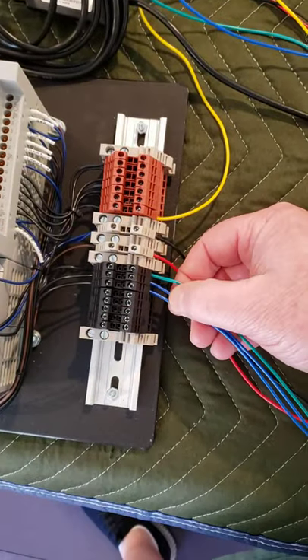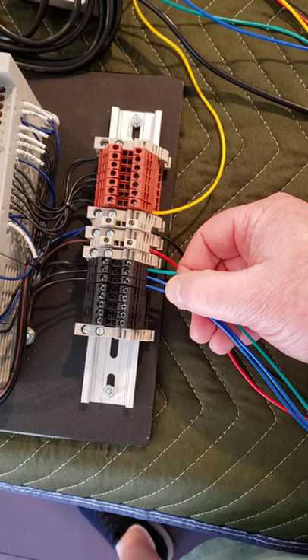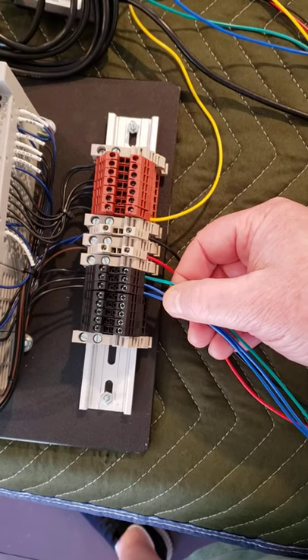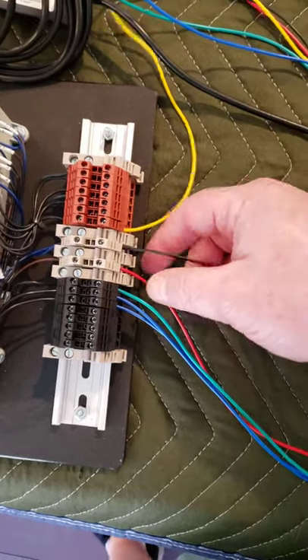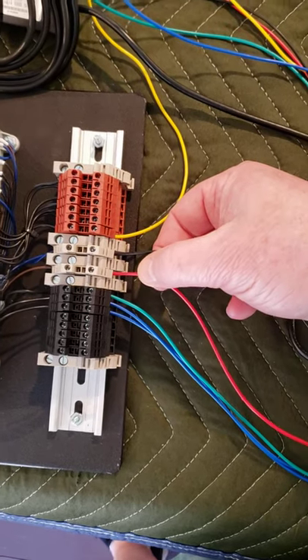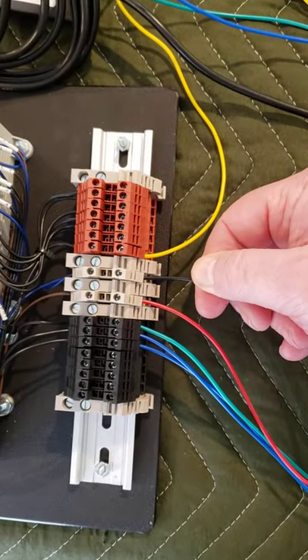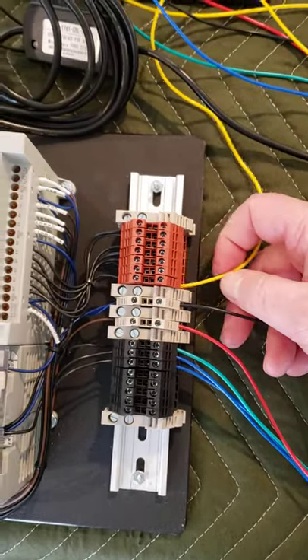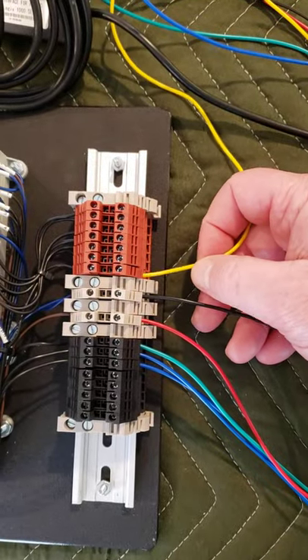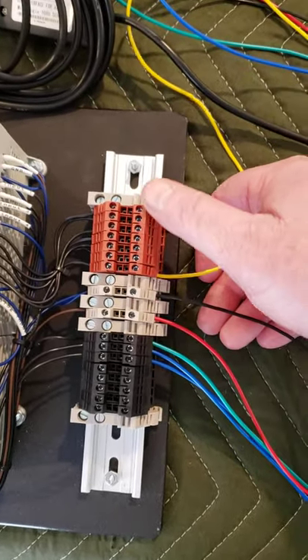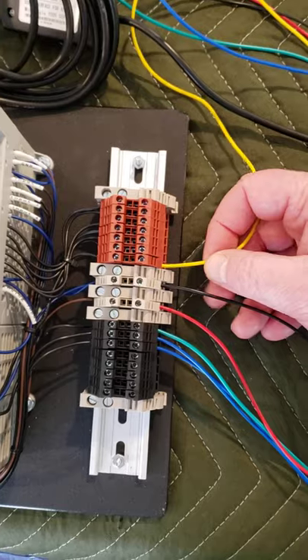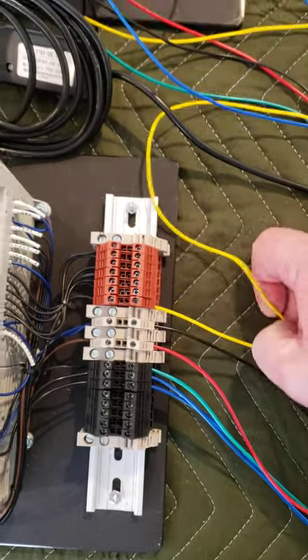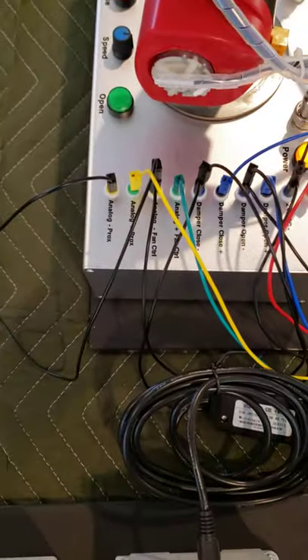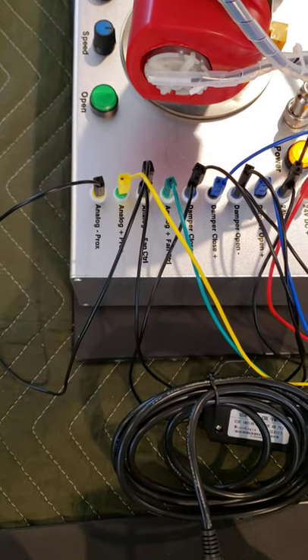The two blue wires are the valve open and close contacts. The red wire is a positive coming back from the power supply on the PID trainer. The black is going to be the common coming back. And then the only input we're using, and the rest of them are all spares, is the yellow one. And that's going to connect to the proximity switch coming back.